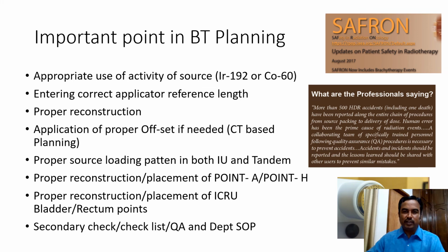So when we do the brachytherapy planning, we have to be cautious and very keen on certain steps. It includes using the appropriate activity or the correct source for the particular unit, especially when you have 2 units in your institution. We have to enter the correct reference length for the applicator used for that particular application, and we have to construct the applicator properly as per the commissioning details.